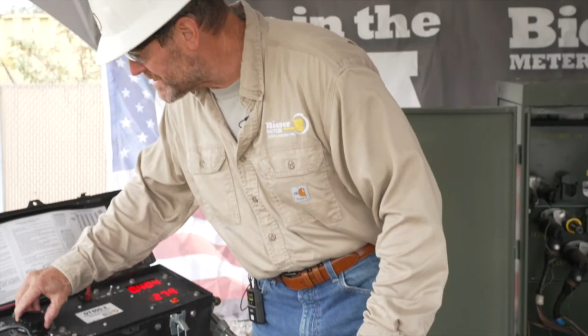So what I'm going to do is crank this down. It requires to properly test. This is a number 2. We suggest you all use a number 1 or 2 aught because it's less flimsy and the strands will not tend to break under that jacket as easily if it's stiffer.